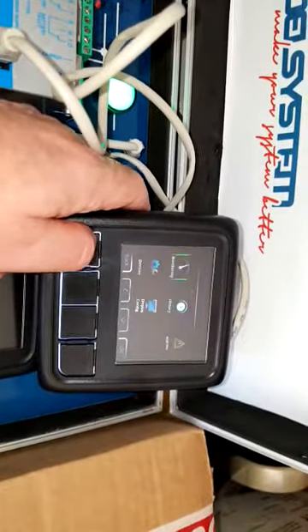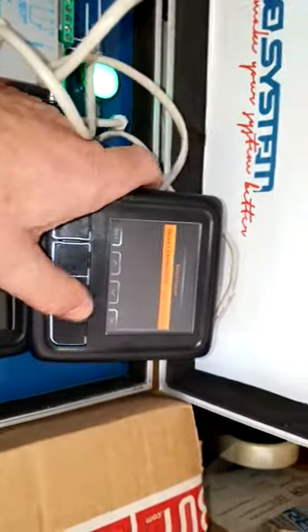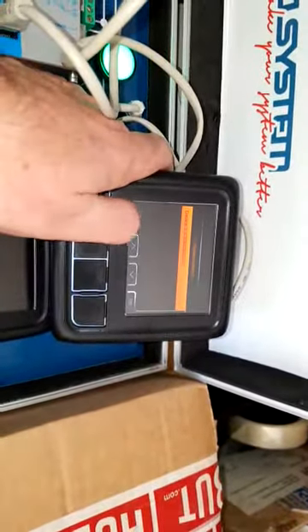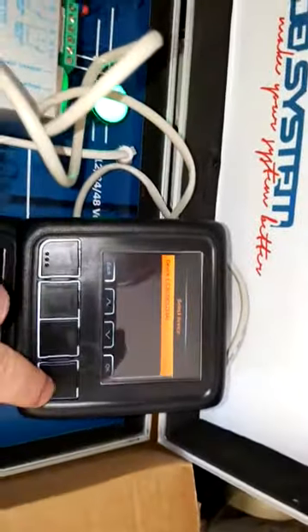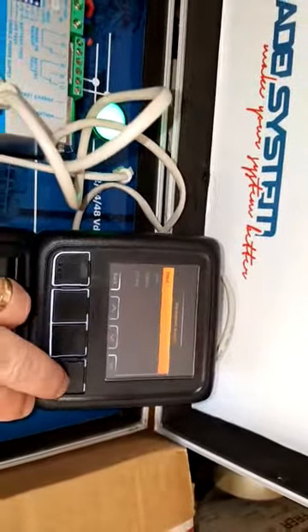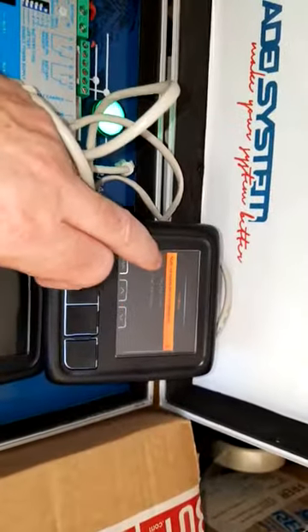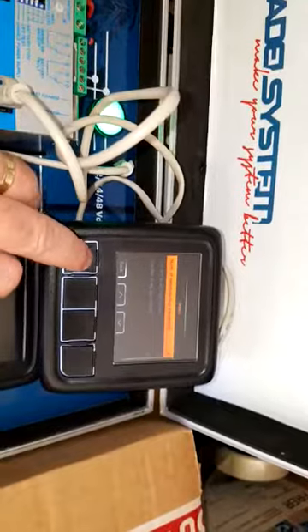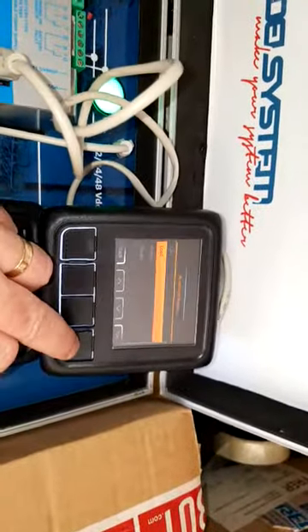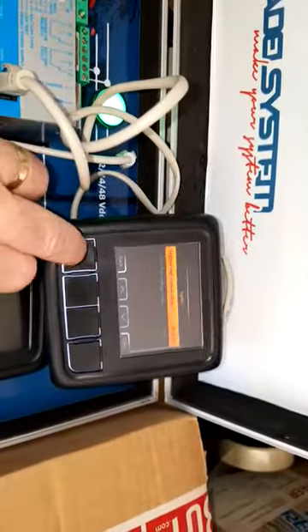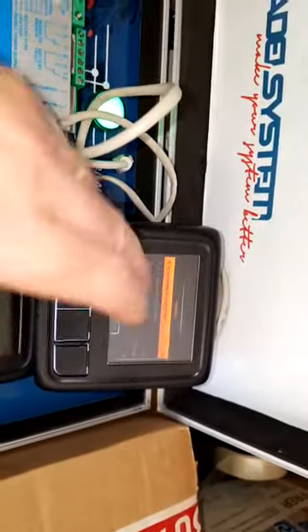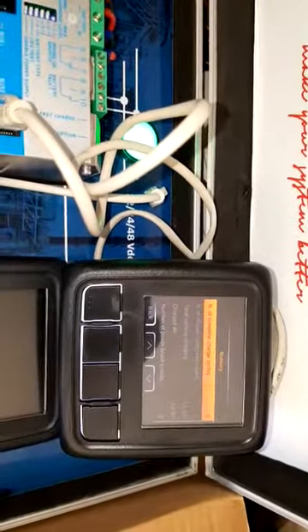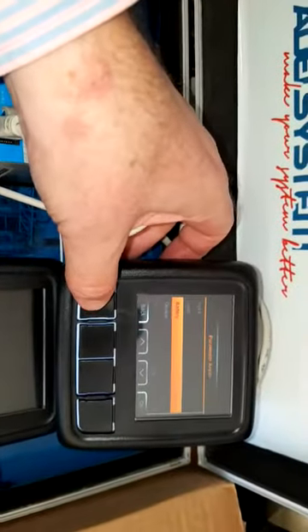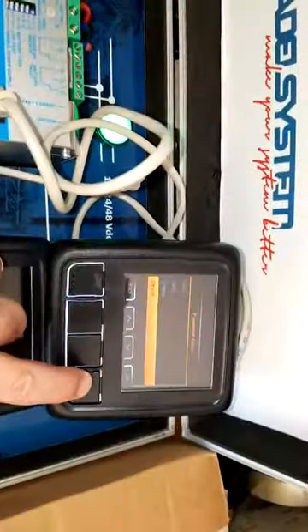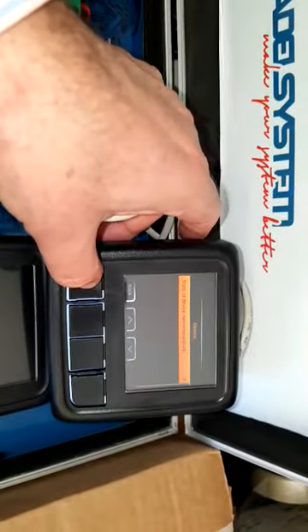And then you have the history. History will tell you what's been going on with the device. This display can take multiple devices, so you can have as many as you can get on a Modbus network. For this device, it'll tell you the input and AC high and AC low events, which you were looking for alarms for. On the load side, it'll tell you the highest load voltage and the lowest load voltage. For the battery, it will tell you the number of completed charge cycles, the number of cycles interrupted, total running time, charge ampere hours, and the number of boost events. And then the device itself will tell you the number of device over temperature events.